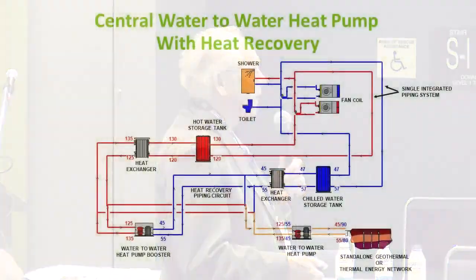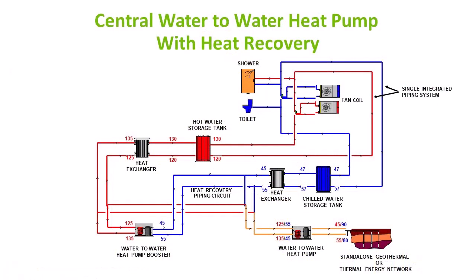Great. Interestingly enough, though, when we're cooling the building, this chill water is coming off at about 55 degrees. What if we ran that into the booster and recovered all that waste heat? So this little guy does 2 things. It boosts the temperature in the winter to give us good temperatures for heating, and in the summer we can recover it. So that's a full heat recovery system in terms of reusing the wasted heat in just the space heating system.